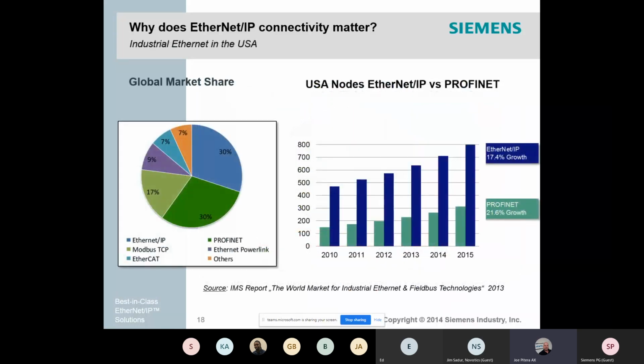Looking at the industrial Ethernet market, globally speaking, Ethernet IP and Profinet have virtually equal market share. In the US, Ethernet IP has a larger installed base than Profinet does, almost 2.5 times. But in recent years, Profinet has increased their base here in the United States by 21.6% growth. Customers do not necessarily choose Ethernet IP over Profinet. However, when they standardize on Rockwell PLCs, the Ethernet IP network becomes the de facto interface. Siemens products talk both protocols with the same unit. This is what customers should care about in this workshop. One hardware configuration, just swap out the PLC to cover most of your needs.